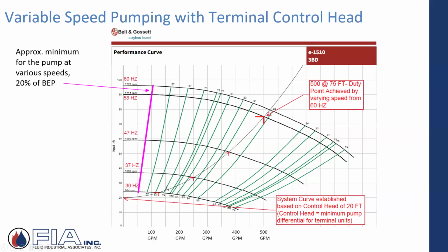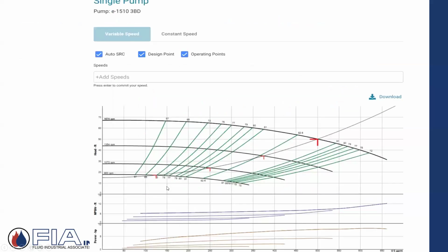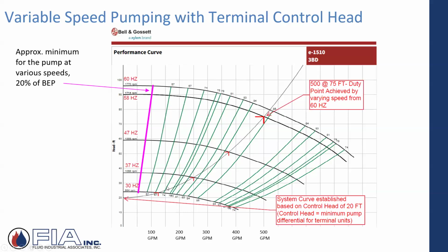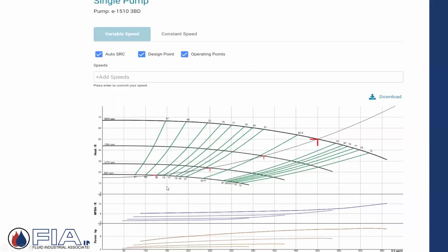So typically, as that speed reduction takes place, these curves take place, and I'm following that curve down, I typically don't want to be anything less than 20% of BEP. So depending upon where that 500 falls, I might be operating down to as low as somewhere around a little less than 100 GPM relative to the 500 gallons a minute. But I'm always going to be at that 20 feet of head. I always want to provide that control head, they call it.